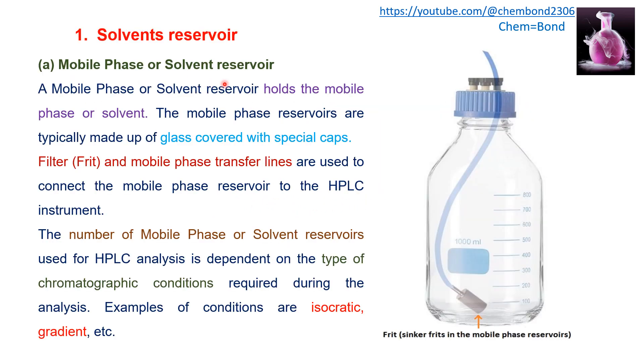The mobile phase or solvent reservoir holds the mobile phase or solvent. The reservoirs are typically made up of glass that is covered with special caps. There are two other components of the mobile phase reservoir: the filter or frit, and mobile phase transfer lines. The filter or frit will filter out any dust or particulate particles if they are present in the mobile phase.